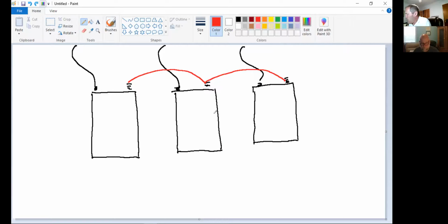Okay, what's the procedure as far as opening or closing transformers in closed delta? What is the step process? So we said we had lighting, we had power, and we had power. So what's the procedure, and it doesn't matter left to right. Somebody let me know which transformer you're going to de-energize first. The right power, or the left power, and then the right power, then go to the left, and then the lighting. It doesn't matter, you are totally correct.